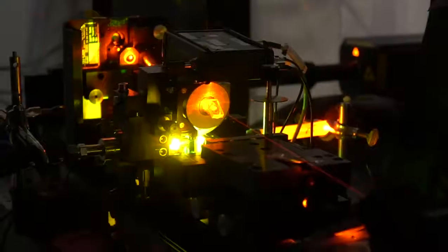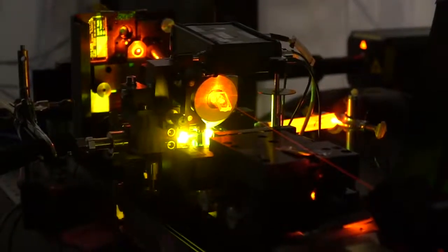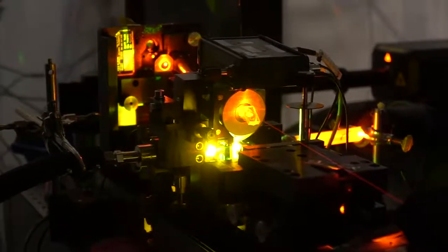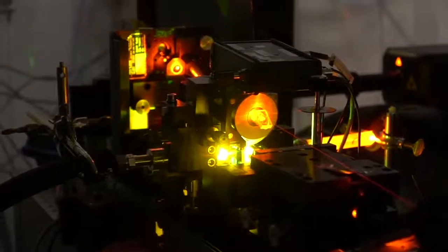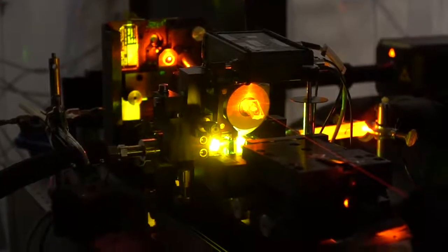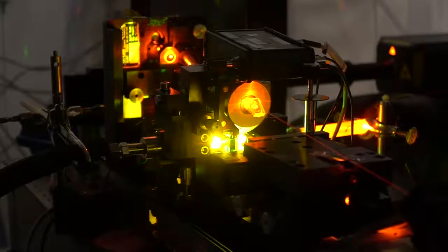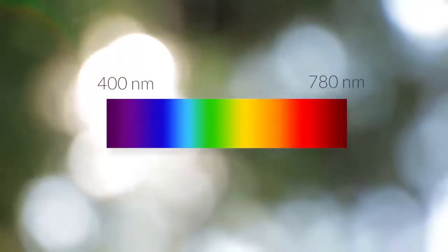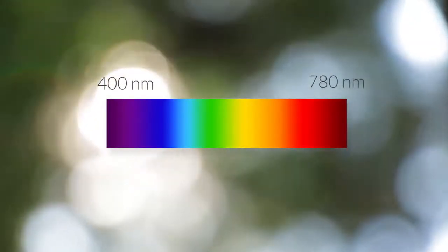Depending on the class and specifications of the laser that you will operate, different eye-related hazards may dominate, since different wavelengths of light interact with different regions of the eye. Laser light can therefore be dangerous for the eye across the electromagnetic spectrum. However, one range that poses particular danger is visible light, spanning approximately 400 to 780 nanometers.